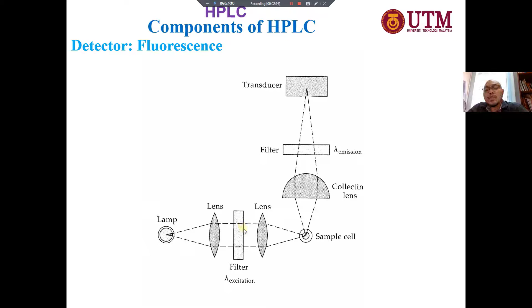Okay, if, for example, we put the detector over here, we will have interference from the lamp, because we need to measure the wavelength emitted by our sample, but we cannot avoid the radiation produced by the lamp. So that's why we need to put it at a 90 degree angle.